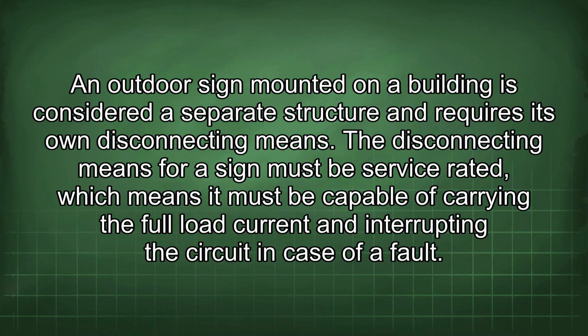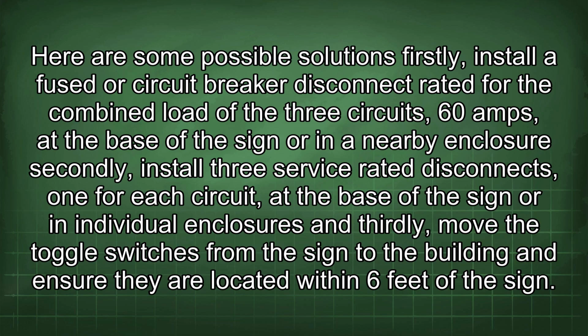An outdoor sign mounted on a building is considered a separate structure and requires its own disconnecting means. The disconnecting means for a sign must be service rated, which means it must be capable of carrying the full load current and interrupting the circuit in case of a fault. Here are some possible solutions.